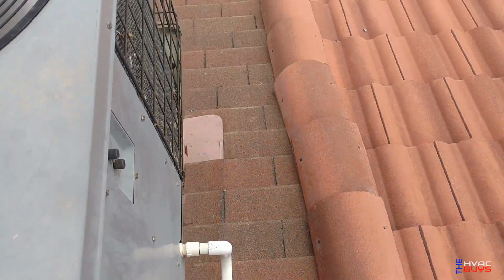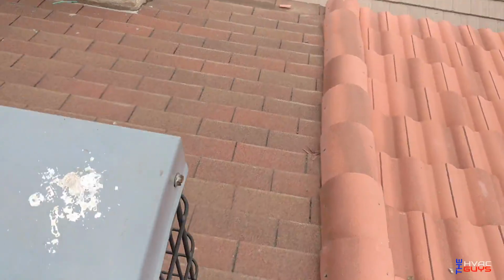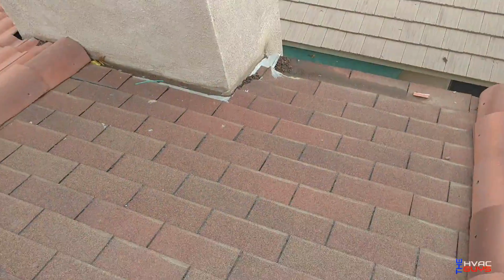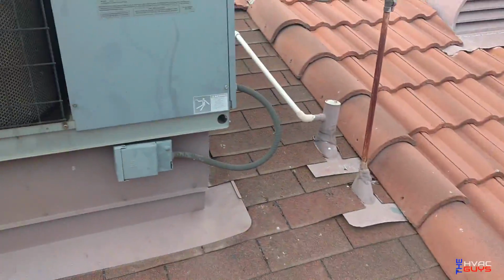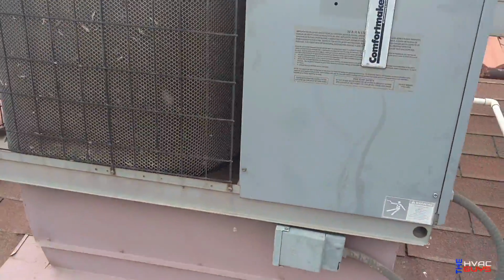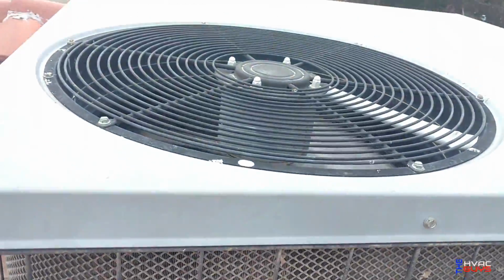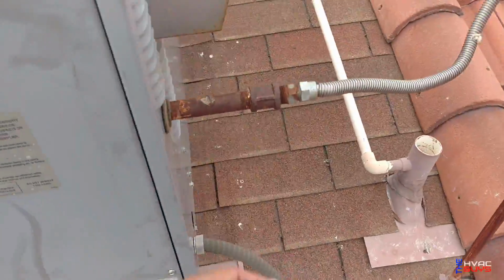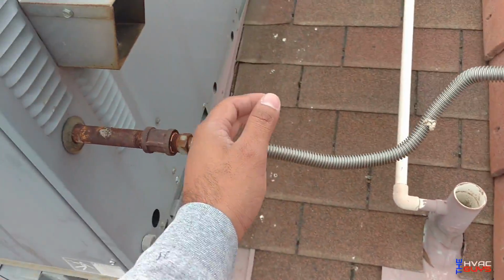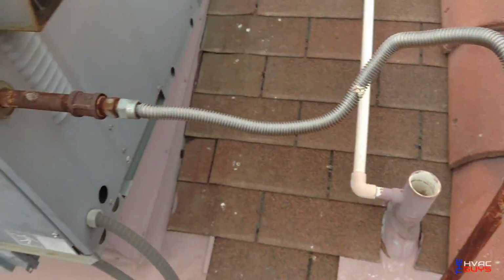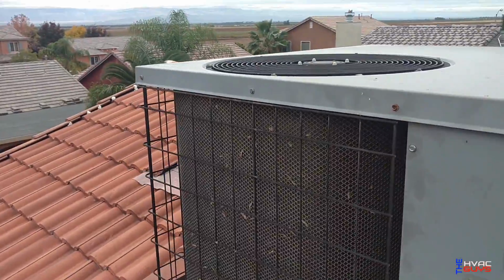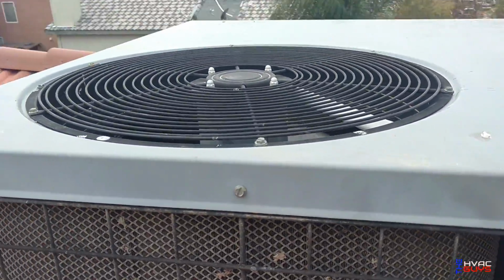Okay guys, so we're here on this unit where the AC stays on. What they were doing was shutting the unit off through the breaker, so you can see us switching the breaker on and the heater's on as well. So we're gonna pop this open and see if something's bypassed.